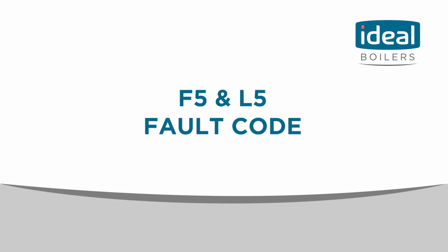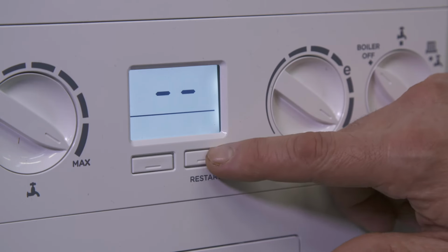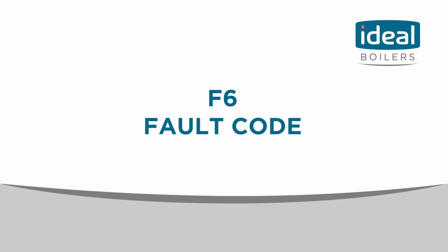If you encounter an F5 or an L5 fault code, it indicates a return thermistor fault code. Try a restart. If the fault code reoccurs, contact Ideal Boilers. If you encounter an F6 fault code, it indicates a fault with your outside sensor. Try a restart. If the fault persists, contact Ideal Boilers.